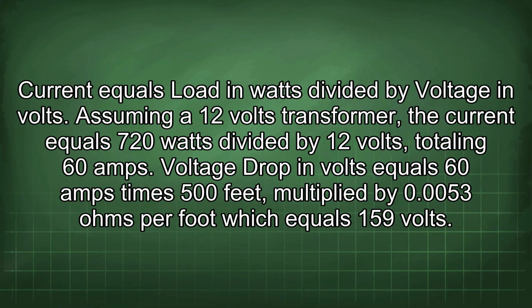Current equals load in watts divided by voltage in volts. Assuming a 12 volt transformer, the current equals 720 watts divided by 12 volts, totaling 60 amps. Voltage drop in volts equals 60 amps times 500 feet, multiplied by 0.0053 ohms per foot, which equals 159 volts.